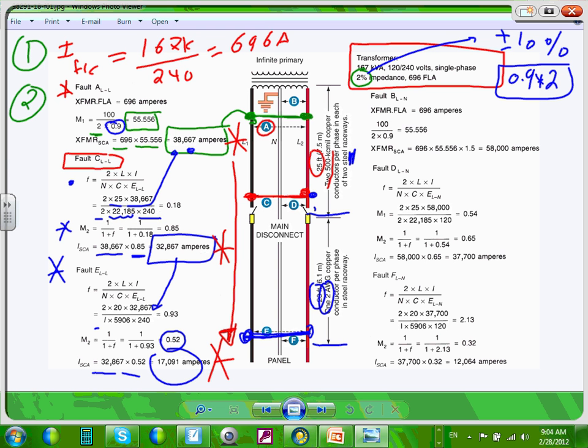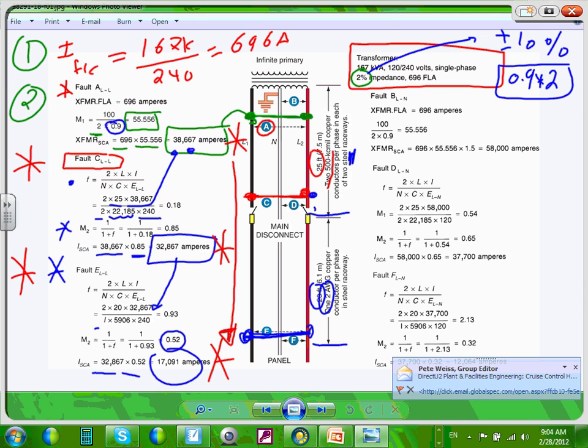Any question about that? What you see on this side is for the ground, line to ground. This is line to line. Line to line is when you take hot with hot and you tie them together. A ground fault, so we took a calculation at point C and at point E. At these 3 points, A, C, and E, calculation.